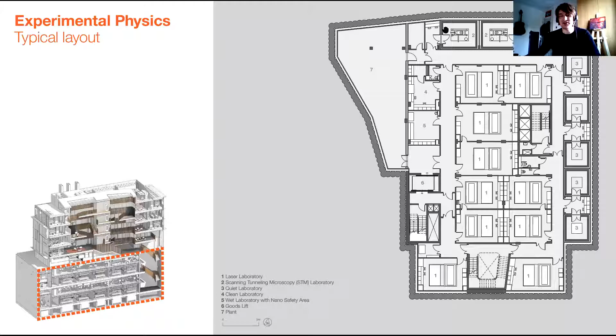So each one of those research elements had its own unique challenges. The quantum computers require incredibly stable environmental conditions, and the high resolution scanning requires incredibly tight vibration standards, and we'll just come on to the reason behind that a bit now. So this is a typical basement floor plate, and the quantum computer laboratories are in the middle, and then the scanning rooms around the perimeter. So quite close vicinity to each other, and those are the two main laboratory types. And we'll just come on to that now.